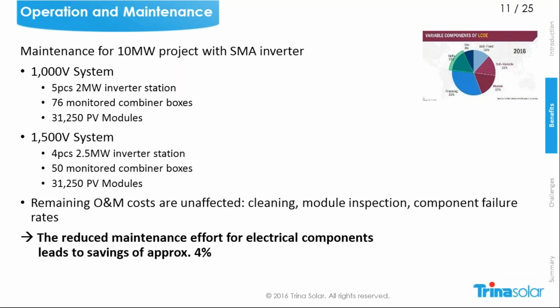If you now take a look at the operation and maintenance, so we are now impacting the OPEX costs, we make a comparison here between a 1000 volt system and a 1500 volt system. This is based on an example from SMA. For a 1000 volt system, they have an inverter station, which is a package with inverter, transformer and substation. They offer it with a size of 2 megawatt. For the 1500 volt system, it will be 2.5 megawatt. So the number for a 10 megawatt project gets reduced from 5 to 4.